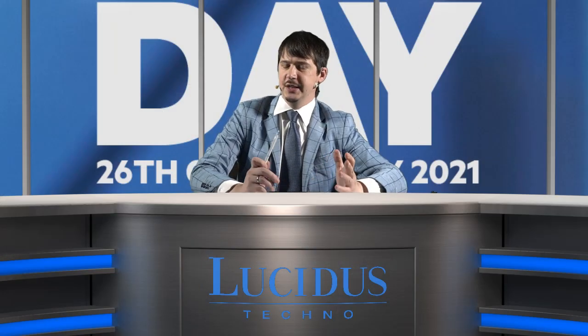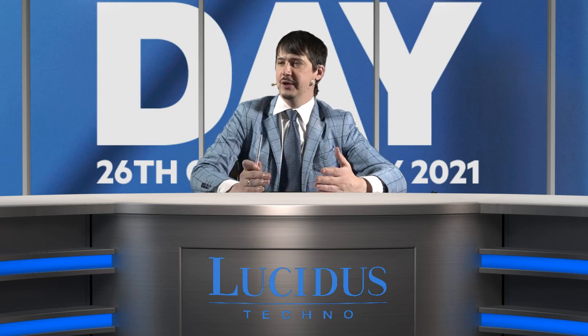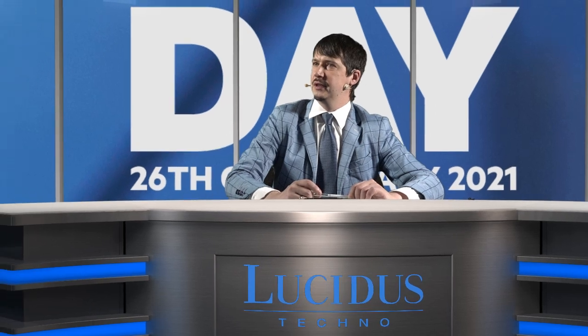But can it also send separate signals, one for switching the light and a second for the security system, in case movement is detected when it shouldn't be, or when it's on security? Is it possible with DALI sensors? We're offering two kinds of detectors. We're offering the standalone, and the standalone is a standalone. That means the detector operates in the room and only for this room. If you want other functions, as shown at the beginning of the presentation, you need the DALI BMS detectors. That means the DALI BMS detector is connected up to a BMS system. In that case, it is the BMS system that actually provides the information on what you want. The detector is kind of a dummy, only a slave. It doesn't have any intelligence built in. The intelligence is in the BMS system.